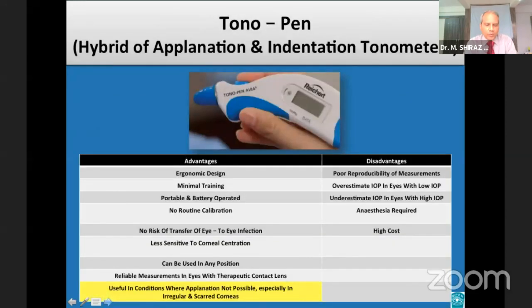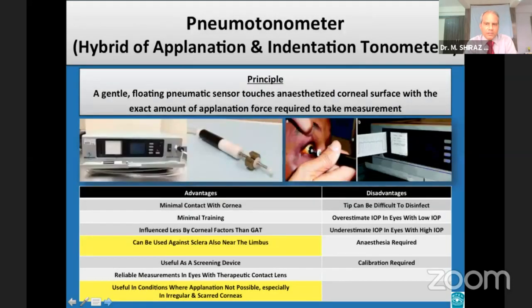The Tono-Pen is an electronic portable version of the Mackay-Marg tonometer. It is particularly useful for irregular corneas as the area of applanation is small, about 2.36 mm squared. The pneumotonometer measures IOP by calculating the force required to flatten an area of cornea using an elastic membrane inflated with gas or air.